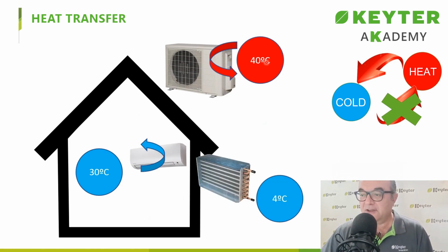Well, what a heat pump does is, in its interior coil, which is inside what is typically referred to as a split unit, it has a coil where the gas changes from liquid to gas state, it evaporates, thus capturing energy. That energy capture, for those of you who are not very knowledgeable about this topic, we can consider as creating a cold surface, for example, at 4 degrees.